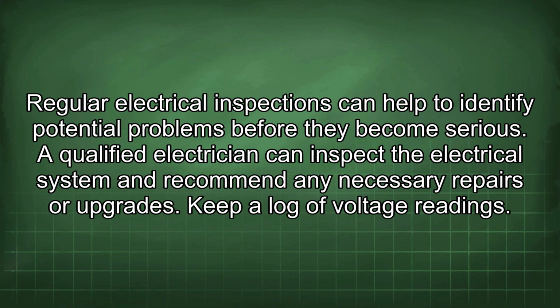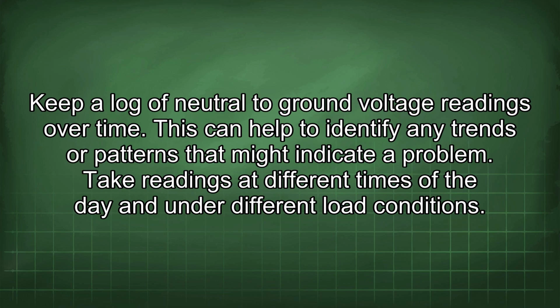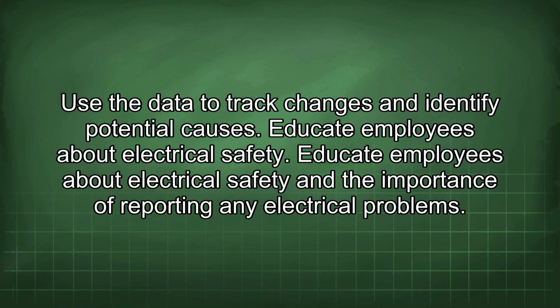Keep a log of voltage readings. Keep a log of neutral to ground voltage readings over time. This can help to identify any trends or patterns that might indicate a problem. Take readings at different times of the day and under different load conditions. Use the data to track changes and identify potential causes. Educate employees about electrical safety.